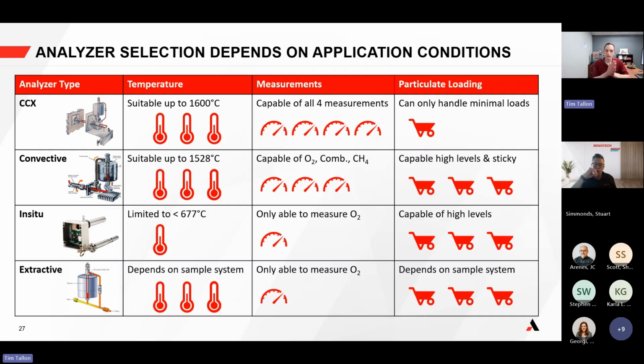And then finally, with the extractive type, it really depends. As you see higher levels of temperature and higher demands on particulate, you have much more complexity built into the process and into the system for the flue gas analyzer. It could potentially handle higher temperatures, you could potentially have a rack with other measurements too, and handle much higher levels of particulate, but it's going to absolutely drive complexity in the design of the safety, the sampling system, and also the time and costs around that, let alone training.